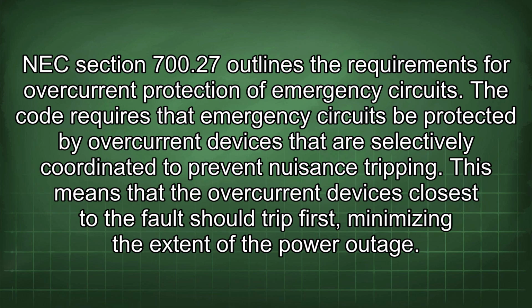NEC Section 700.27 outlines the requirements for overcurrent protection of emergency circuits. The code requires that emergency circuits be protected by overcurrent devices that are selectively coordinated to prevent nuisance tripping. This means that the overcurrent devices closest to the fault should trip first, minimizing the extent of the power outage.